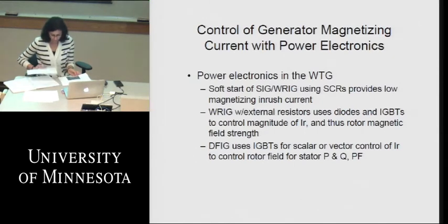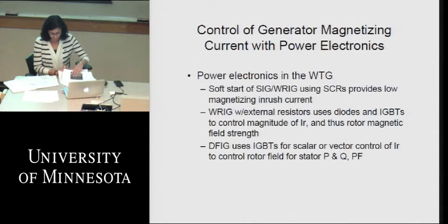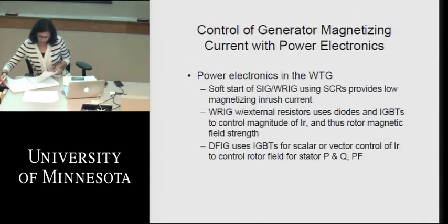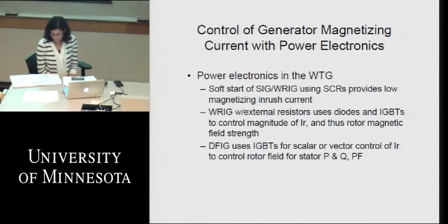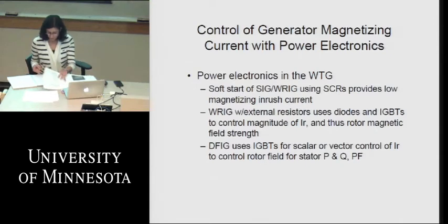So the controls we have also, we put a lot of power electronics into these modern wind turbines. I'll just go through the bullets quickly, but we use them for soft starting. So we put silicon-controlled rectifiers on these Type 1 and Type 2 wind turbines that have very little control to them. Since they're simple induction machines, they'll pull a large VAR draw when the core magnetizes. And if we can slowly pull that current into the generator to magnetize the core, then we can reduce the inrush current from anywhere from 8 to 10 times to maybe only 4 to 6 times. And this is a great benefit because every time we're drawing that current off of the grid to magnetize the core of every one of these wind turbines, it will tend to change the voltage quite a lot until the core gets fully magnetized. And so it's a way to keep our power quality and be a good player on the grid.